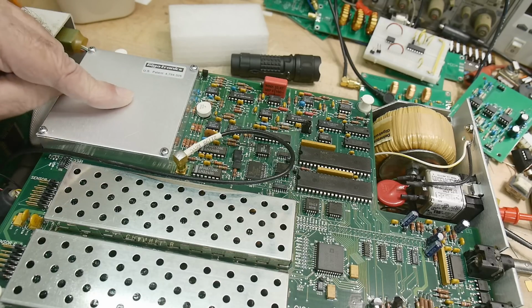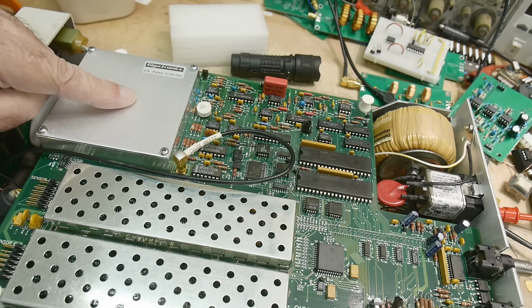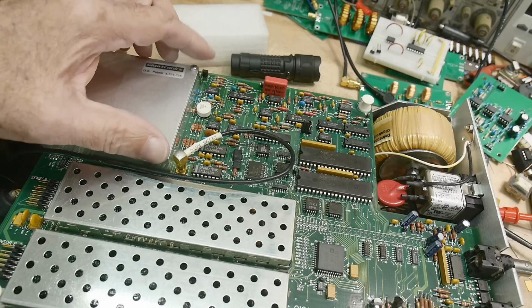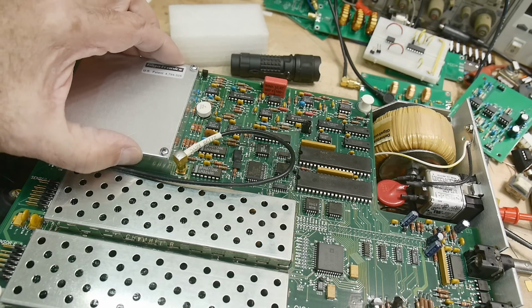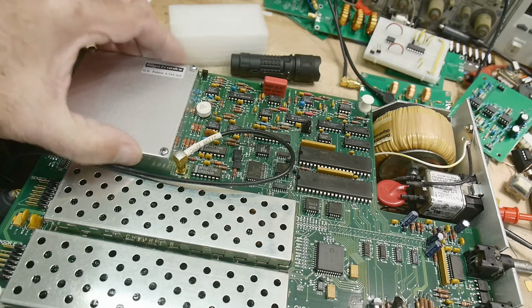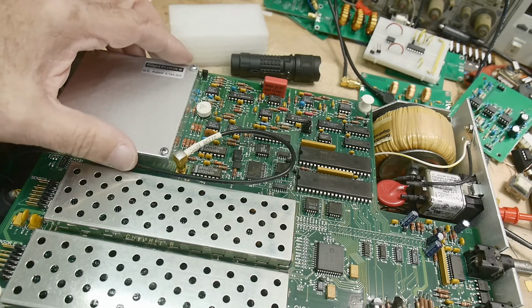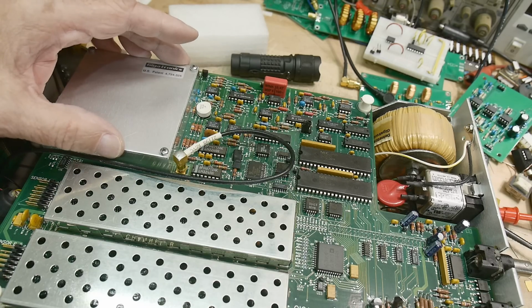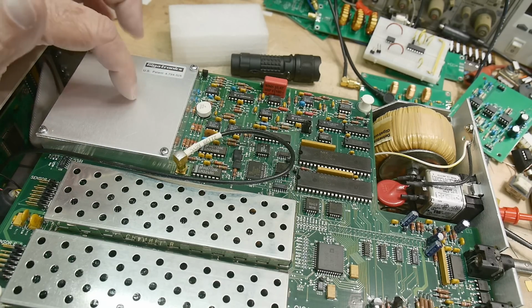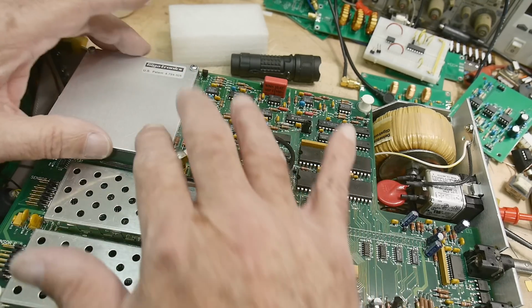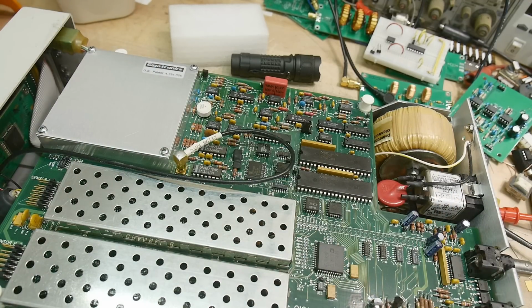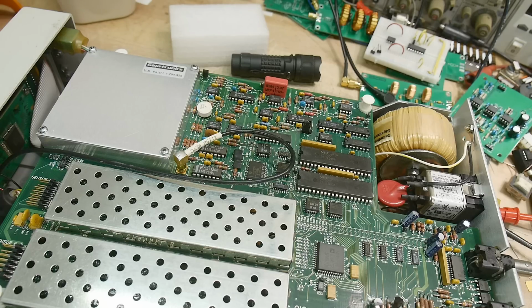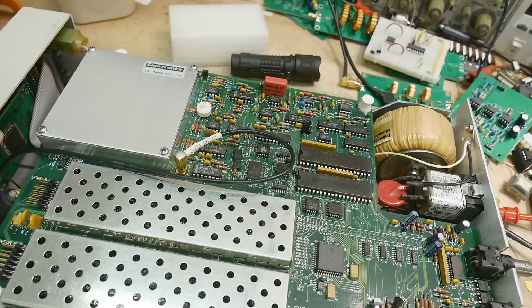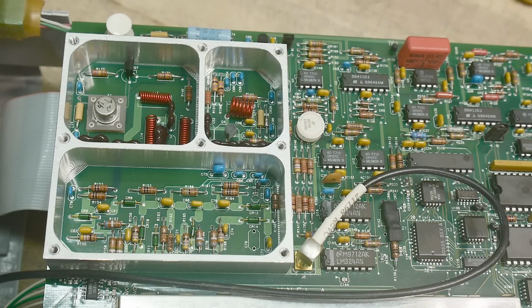So this is a thermistor-based power meter that's super, super accurate, but it just does not have very much dynamic range. And so you use this super accurate 0 dBm reference, and then you apply it to all the other ranges. Well, how do you apply it to all the other ranges? Well, you have a very precise step attenuator. Okay, so under this can is both the power meter inside the power meter and the step attenuator. And by having a power meter inside the power meter, that's how you get to the accuracy that this thing had, which was quite good. Yep, they didn't touch that a bit. Nobody's going to touch this thing.